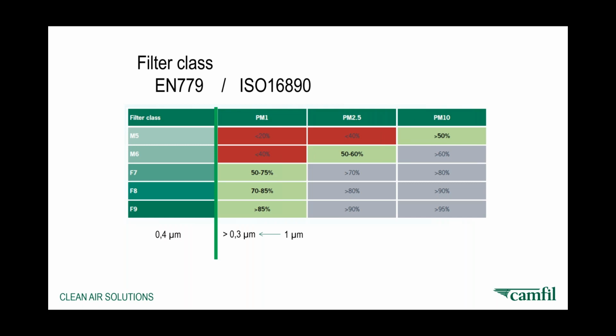And for this webinar, we're not going to go into the full details of the standard. There's just a table here to look at. People that are familiar with filters would have previously been using M5, M6, F7, F8, F9 as the type or classification of a filter. And that's now changed with the new ISO 16890, which is a global standard, fully introduced globally and fully introduced since the beginning of last year in Europe for both design and existing buildings. Here we're classifying the efficiency of a filter according to an actual particle size. So it's particles between 0.3 and 1 micron, up to 2.5 microns or 10 microns.